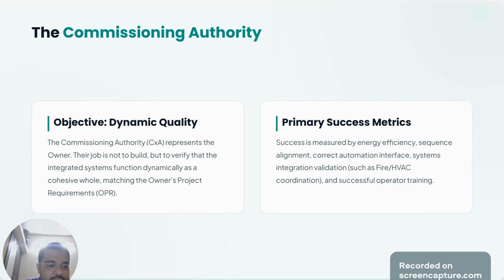So while the site engineer is happy that a pump physically turns on, the CxA is asking: does this pump modulate speed correctly when the cooling load decreases? Does it talk to the building management system? Does it shut down instantly during a fire alarm test? Success for the CxA is about dynamic performance, system integration, and long-term operating efficiency.